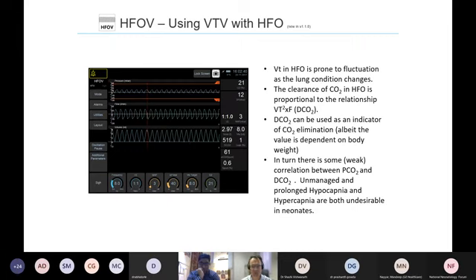The idea here is that in regular high frequency oscillation, the pressure waveform will fluctuate as a result of changing compliance or resistance in the patient's airways. This gives rise to some changes in the amount of CO2 that's being eliminated from the airways. So as those airways become constricted, the CO2 being eliminated decreases, and it might increase as lungs become more compliant. So using VTV with HFO is an approach which ensures that the tidal volume per breath is stabilized in high frequency oscillation, and the pressure is allowed to adjust, while keeping this tidal volume stable.